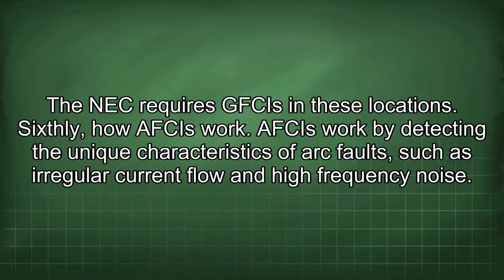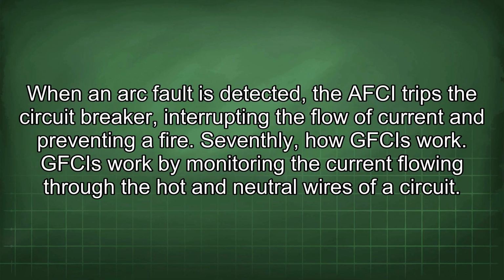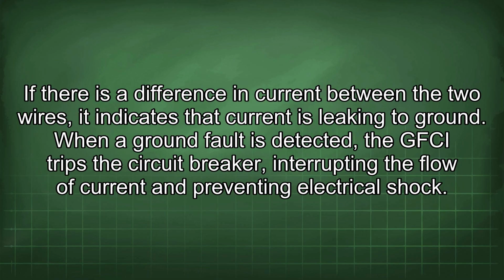Sixthly, how AFCIs work. AFCIs work by detecting the unique characteristics of arc faults, such as irregular current flow and high-frequency noise. When an arc fault is detected, the AFCI trips the circuit breaker, interrupting the flow of current and preventing a fire. Seventhly, how GFCIs work. GFCIs work by monitoring the current flowing through the hot and neutral wires of a circuit. If there is a difference in current between the two wires, it indicates that current is leaking to ground. When a ground fault is detected, the GFCI trips the circuit breaker, interrupting the flow of current and preventing electrical shock.